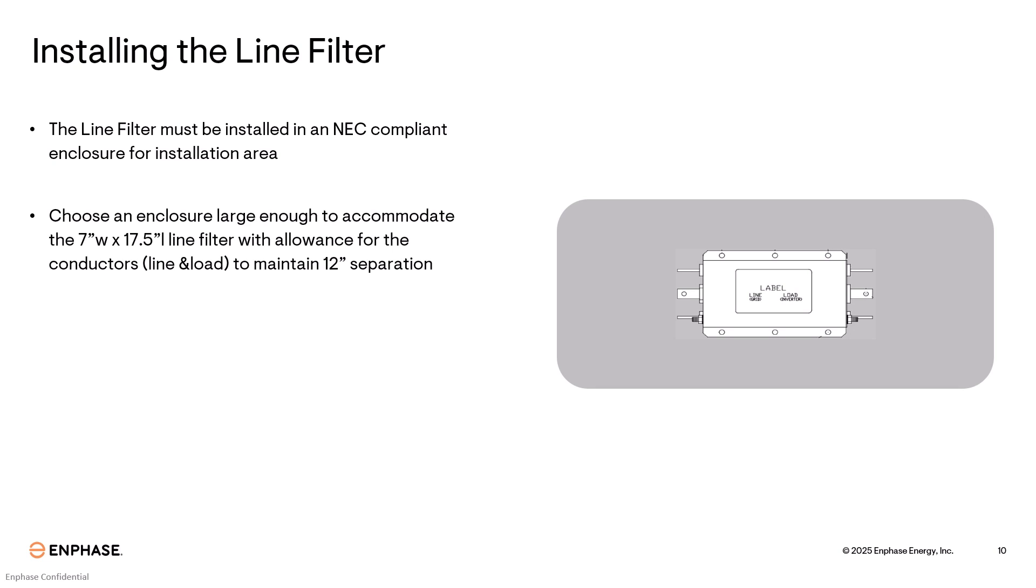Choose an enclosure large enough to accommodate the 7 inch wide by 17.5 inches long line filter, with allowance for the conductors line and load to maintain 12 inches of separation.